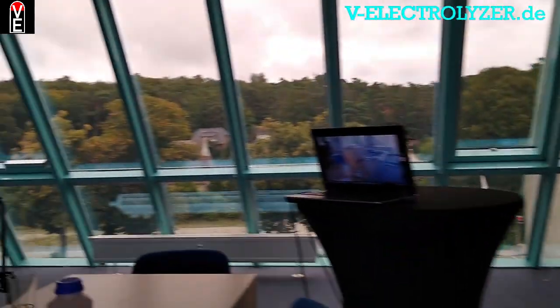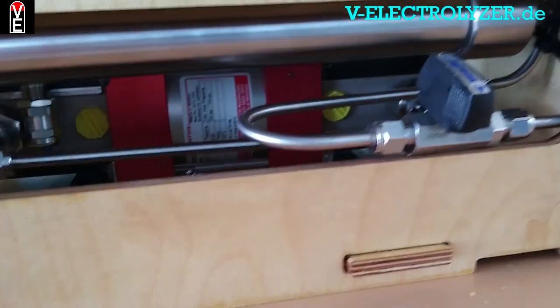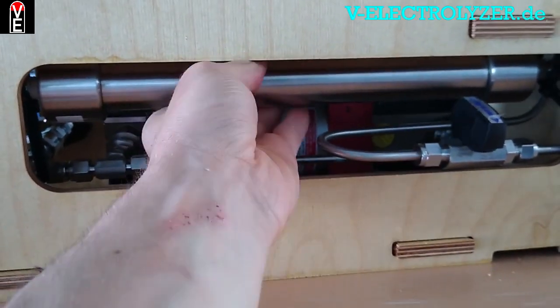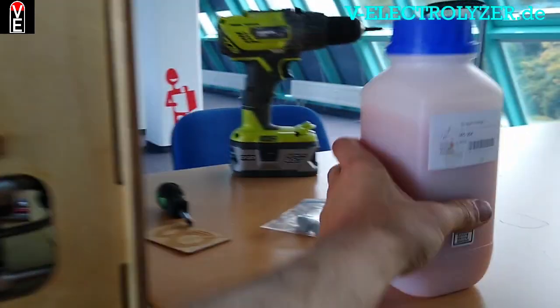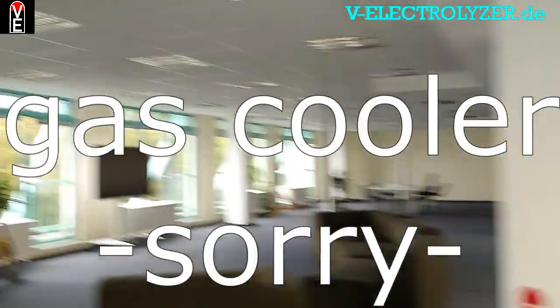This valve you close when you change the second drying system, which is this column. In this column we find silica gel — you can just turn it out and refill it with fresh or baked silica gel, which is orange. When you have refilled it, you open this valve, then the gas goes up into the gas cooler.